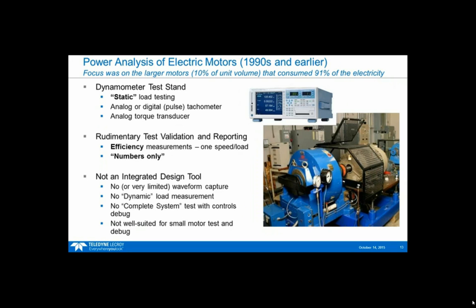Motors historically, especially big ones like AC induction motors, are tested on a test stand. The test is usually what I'd call a static load test, so a single load, and there'd be an analog tachometer signal, an analog torque transducer that would feed data to calculate mechanical power. The thing that calculates mechanical power could be this power analyzer, which would also calculate electrical power for the motor and also calculate efficiency. This is what I'd call not an integrated design tool. Limited waveform capture, doesn't really provide dynamic load measurements. It doesn't allow you to look at control signals that are coincident with the power signals. It's not very well suited for small motor test and debug.